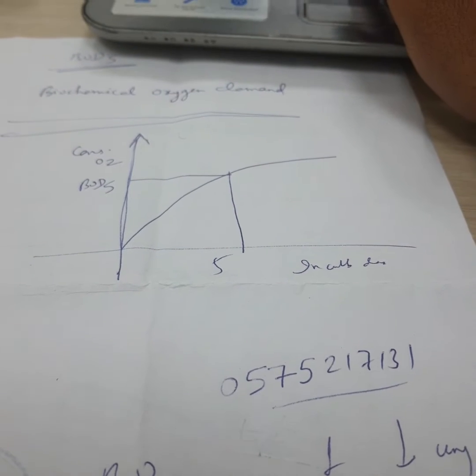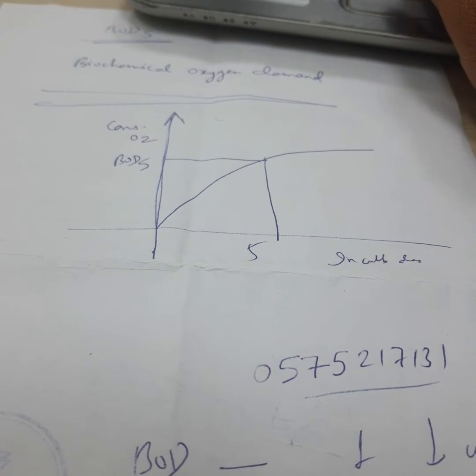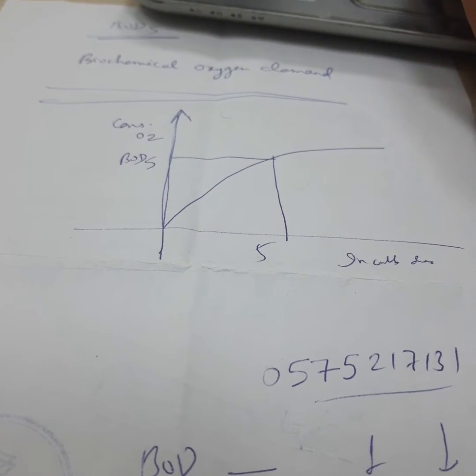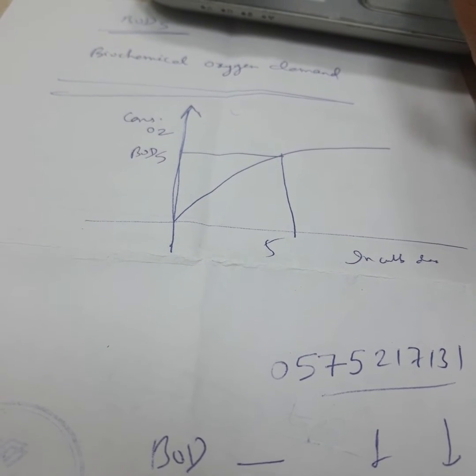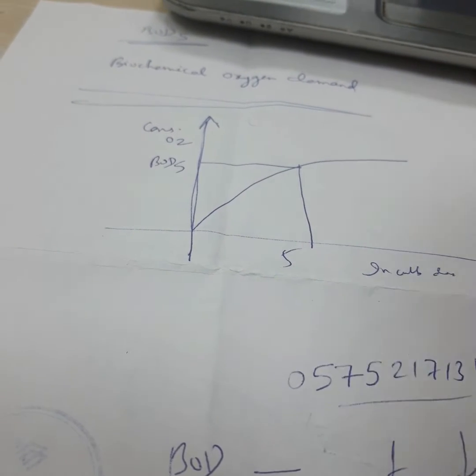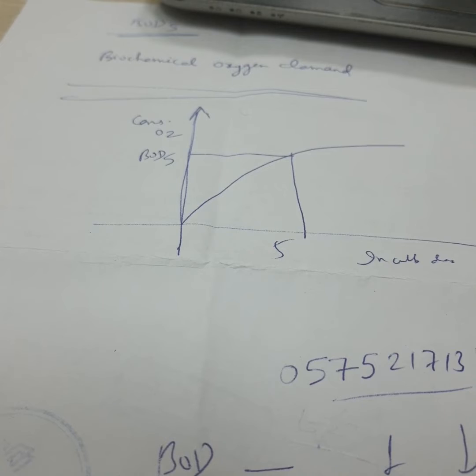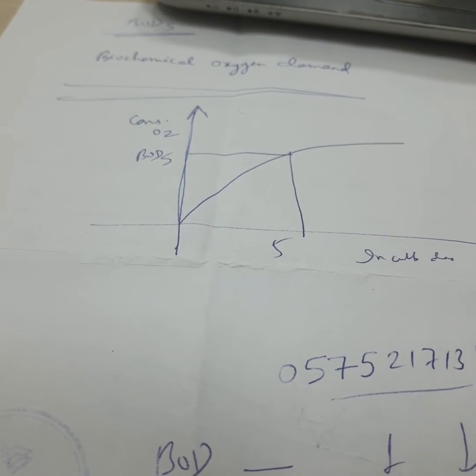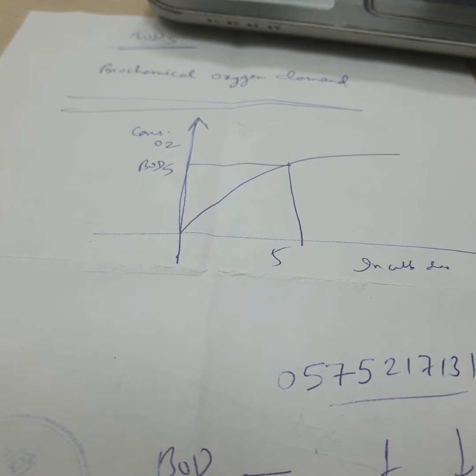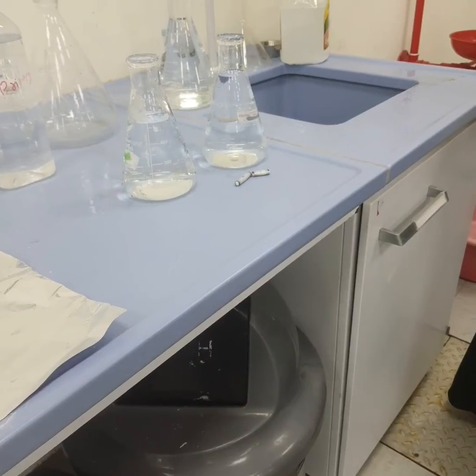In the laboratory we will use the OxyTop measuring system, which is based on pressure measurement — the difference in pressure. This measurement is made via piezo-resistive electronic pressure sensors. The OxyTop measuring system minimizes measuring work and is suited to courses of respirometric BOD measurement. The equipment we will use includes a BOD bottle, an OxyTop bottle, a rubber quiver, sodium hydroxide pellets, and a bead. The purpose of adding sodium hydroxide pellets into the rubber quiver is to absorb the CO2 produced in the process, which might interfere with pressure measurements.